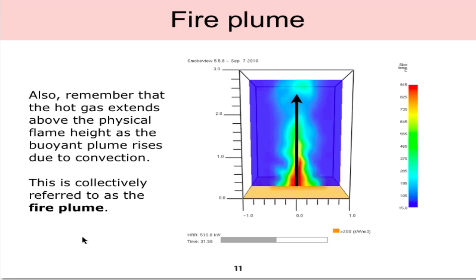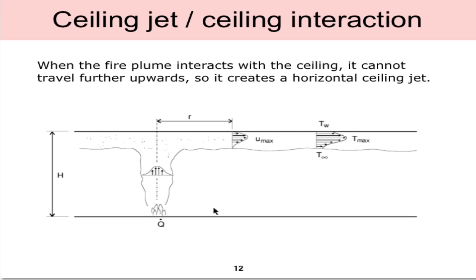Moving on, we remember that the fire plume is not just limited to the physical flame, but that due to buoyancy, the hot gas is traveling upwards, and we collectively refer to these three regions as the fire plume. So what happens if we introduce a ceiling as in an enclosure? The hot gases traveling upward due to buoyancy can no longer travel upwards, so it creates this horizontal ceiling jet that travels in all directions. We have a velocity profile, a temperature profile, all in the ceiling jet, and outside of this area is assumed to be ambient conditions.